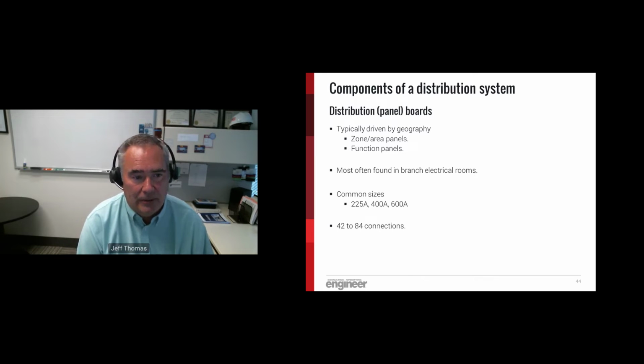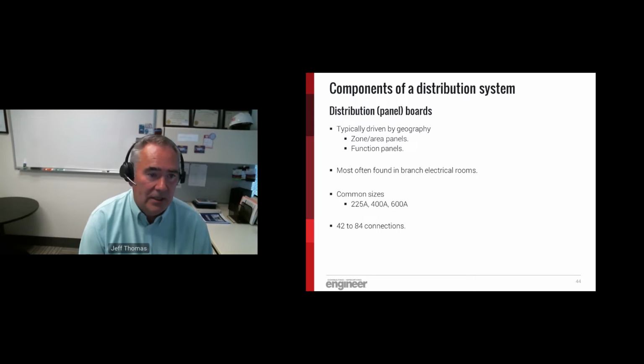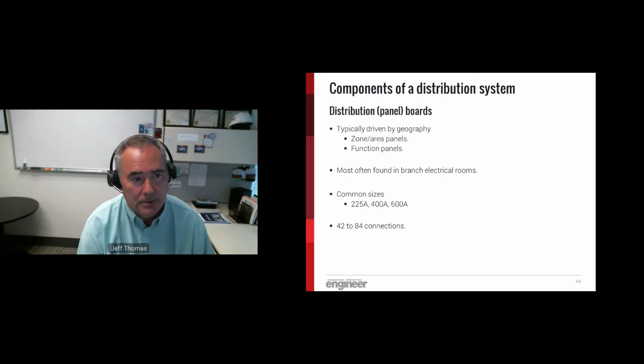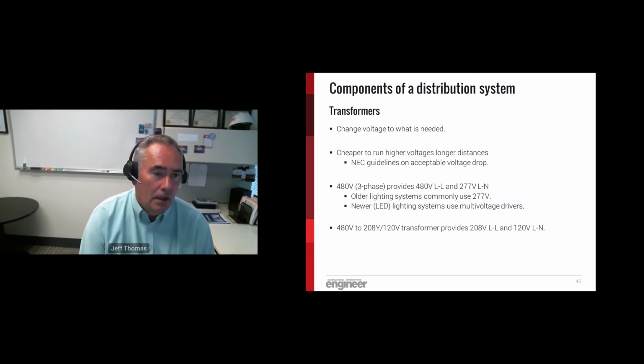And the reason we want to locate these by geography is, as we know, voltage drop is a consideration, and the higher the voltage, the smaller the conductor we can get for the same distance. So we want to be very judicious as we place our panel boards, so we can maintain our costs, okay? Which is why we have transformers, all right? Transformers change the voltage to what we need. It's cheaper to run higher voltages longer distance, and the NEC has guidelines for acceptable voltage drop.